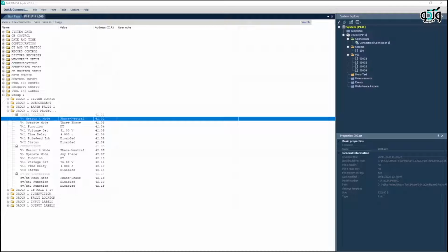Undervoltage protection function test in MiCOM P141 relay. Voltage collapse occurs for various reasons, such as increasing network load, decrease in phase voltage due to fault in the network, complete loss of bus voltage, and similar cases. So protection 27 is intended for different equipment.